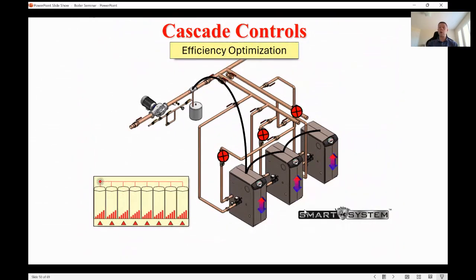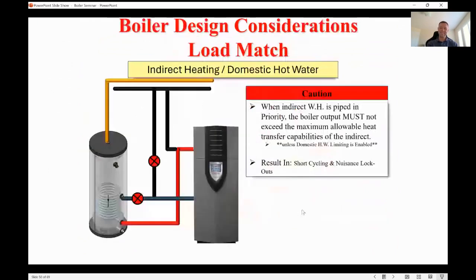Most manufacturers now have another option too, called efficiency optimization. With efficiency optimization, the theory is that any of these boilers are going to be most efficient at their lowest rate of fire, because you're going to have more heat transfer area per BTU provided. So with this type of control scenario, instead of one boiler on at 100% fire, you'll have 3 boilers on at 33% fire, giving you a little bit more efficiency out of it. My personal opinion, I like lead lag, because I found that maintenance is usually more expensive than the gas costs. Because here, you have 3 boilers on as opposed to 1 boiler on, so you're going to have more wear and tear on it. That being said, with the increase in price of gas for all the additional carbon taxes, maybe that'll change soon.